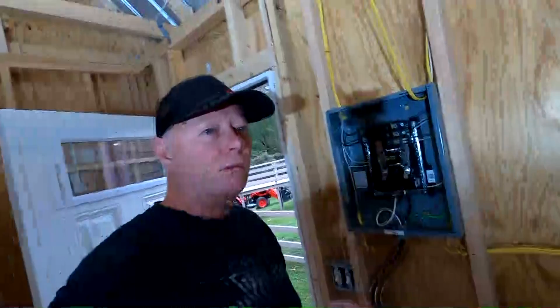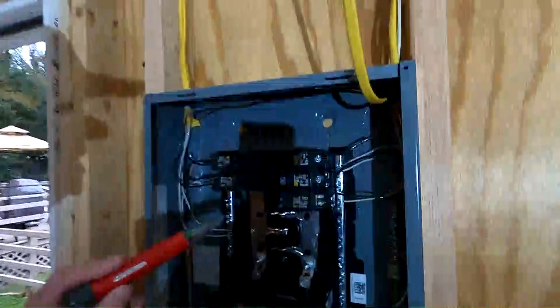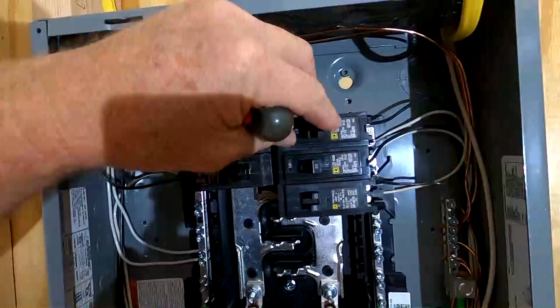So once this voltage, 120 volts on this side for example, comes in and feeds your breakers, you can see these breakers have numbers on them, like the number 20 right there. That's 20 amps of current it will allow to flow through before it trips. Let's say it's on and it gets more than 20 amps, and it trips.